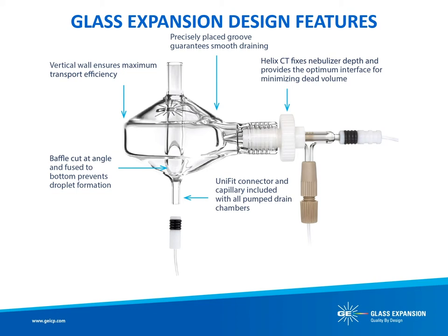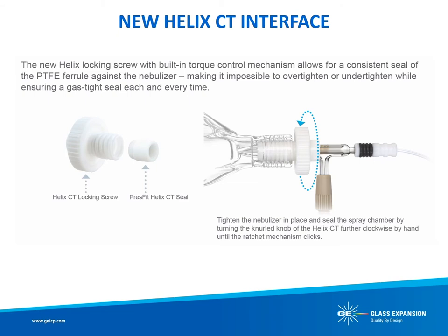With our double-pass cyclonic designs, the Twister and Twinibar, the knockout tube or baffle is cut at an angle and carefully positioned to maximize transport of the aerosol but minimize or eliminate transport of large droplets to the plasma. The Helix CT fitting is carefully designed to fix the depth of penetration and the torque on the nebulizer seal so that the aerosol produced is optimal. All pumped cyclonic spray chambers include our Unifit connector and capillary for smooth and efficient draining. Glass Expansion's new Helix CT locking screw with built-in torque control mechanism was released in 2018.